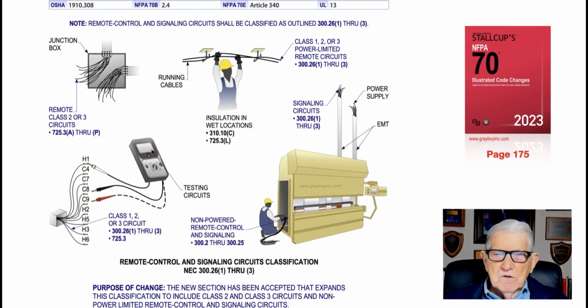Now this illustration deals with remote control and signaling circuits classification in accordance with NEC 300.26, 1 through 3. And the purpose of the change mainly is just to separate the Class 2 and Class 3 from the Class 1. In other words, Class 2 and 3 circuits can be defined and reviewed in Article 100 and Article 725. But a Class 1 circuit now has its own article, which is Article 724. Now, in reviewing the illustration, you see the individual running the conductors, overhead signaling circuits. Well, this points out they could be Class 1, 2, or 3.